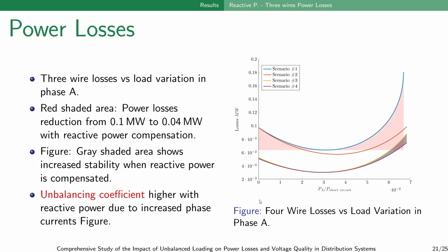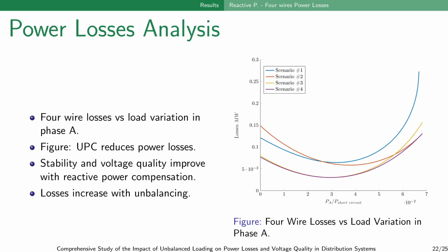The gray shaded area demonstrates the increased stability with reactive power compensation. This figure shows the combined power losses for the four wires. It confirms UPC reduces the power losses and improves the stability and the voltage quality with reactive power compensation.